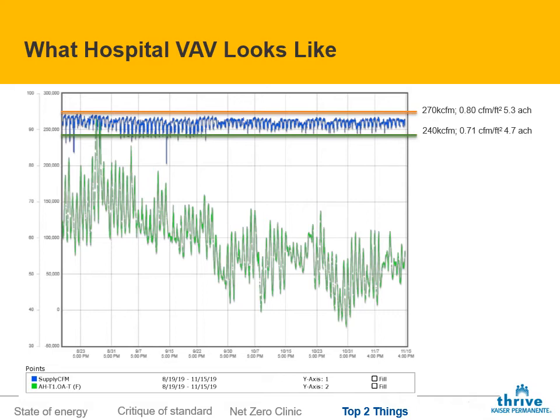That's pretty good. But the lowest number on this graph, barring a couple of those outlier points, is this 240,000 CFM. That's 0.7 CFM a square foot, or it's almost 5 air changes for the whole volume of the building. That's the lowest point on the graph. And the reason I'm showing you this building is because I actually think this is pretty good.